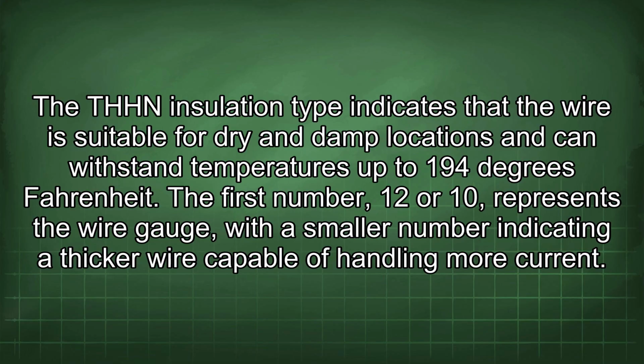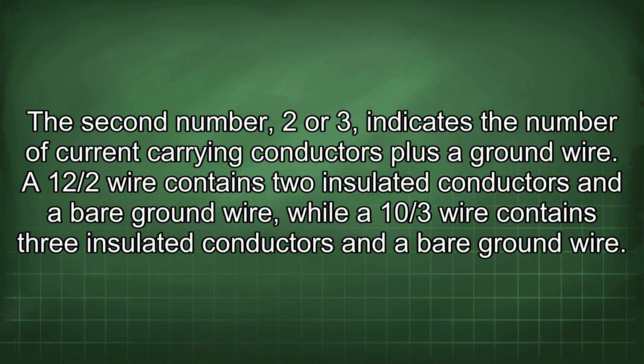The first number, 12 or 10, represents the wire gauge, with a smaller number indicating a thicker wire capable of handling more current. The second number, 2 or 3, indicates the number of current-carrying conductors plus a ground wire. A 12/2 wire contains 2 insulated conductors and a bare ground wire, while a 10/3 wire contains 3 insulated conductors and a bare ground wire.